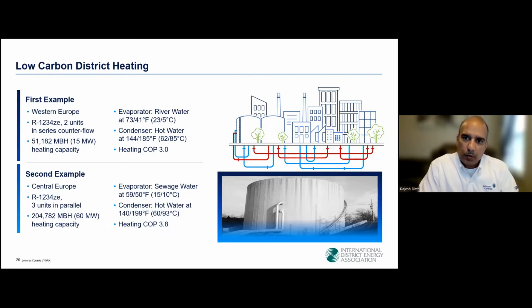The evaporator source is river water, whose temperature fluctuates largely between summertime and wintertime. In summertime, it is about 73 F or 23 Celsius, and in winter, it drops down to 41 F or 5 Celsius. There are 2 compound-style heat pumps piped in series counterflow configuration, delivering 51 million BTUs of heat, which is approximately 15 megawatts, with a heating COP of 3.